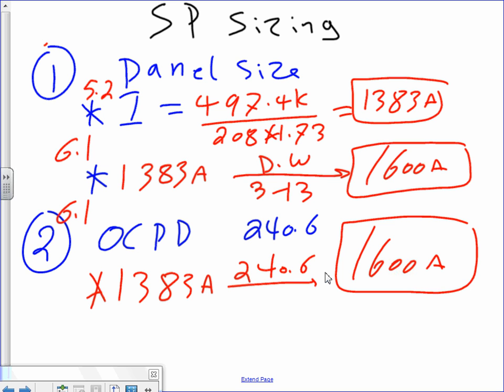Now inside the box, we're going to put the circuit breaker, right? Inside the box, we're going to put a circuit breaker. This is number one. Number two, the overcurrent device. Guys, go to 240.6. That's the NEC code book. Go to 240.6. For 1383, 240.6 gives you 1600 amp. That's the standard circuit breaker.